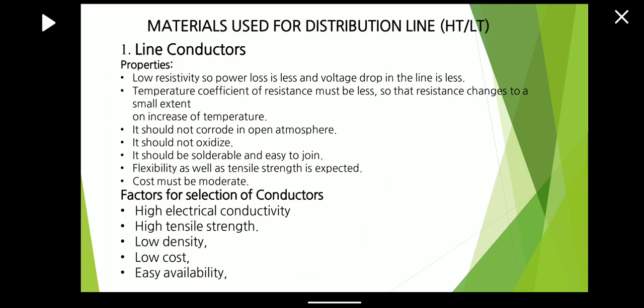What are the properties of the line conductor? First, low resistivity, so the power losses are less and the voltage drop in the line is also less. The temperature coefficient of resistance must be less so that the resistance changes to a small extent on the increase of temperature. It should not corrode in the open atmosphere, it should not oxidize, and it should be solderable and easy to join.